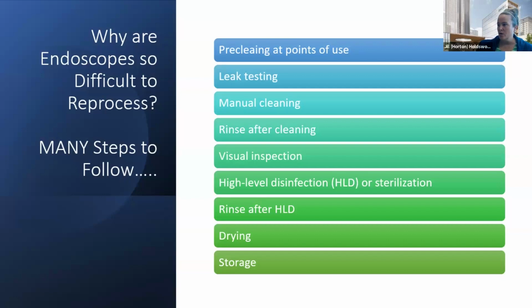So we have to make sure that pre-cleaning is occurring and it's occurring correctly. And oftentimes, if I'm the one that's in the reprocessing room, I may not have complete control over what's going on at the pre-cleaning. And so that's where someone like myself, an infection preventionist or a leader in the department, really has to pull a team together to make sure all steps are being followed. And this oftentimes is why it fails, because you have to have somebody that's helping pull everything together and tie a nice bow on all of these steps. So is the pre-cleaning happening, and is it happening correctly?